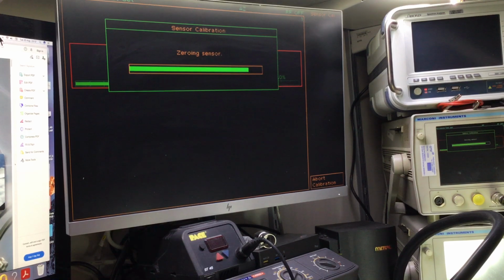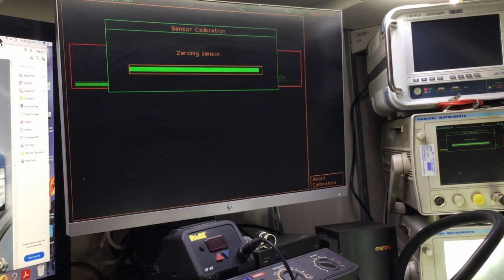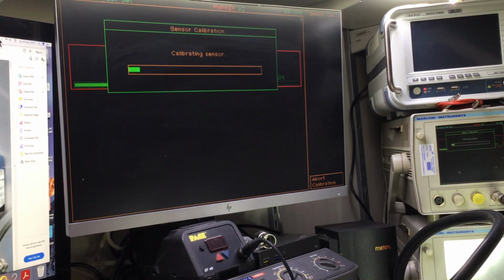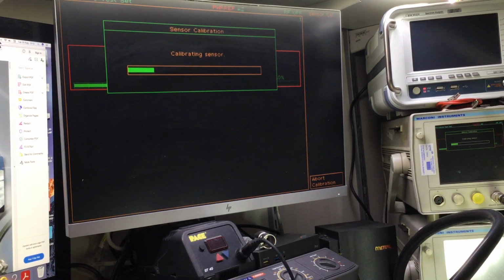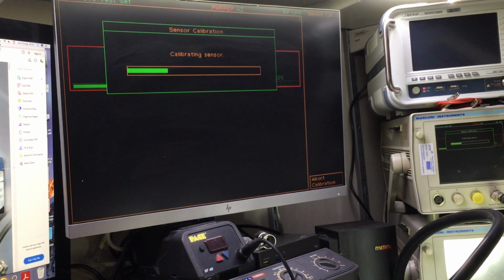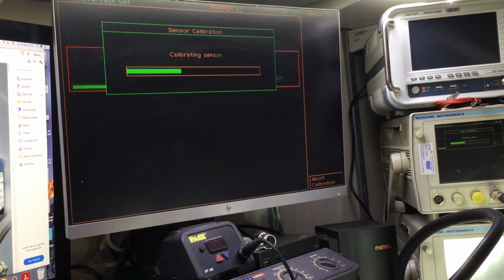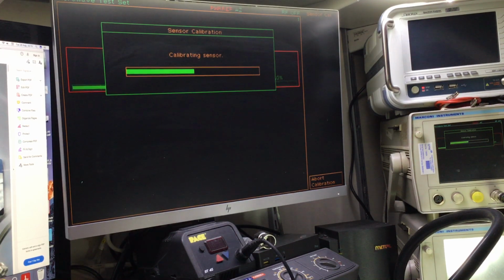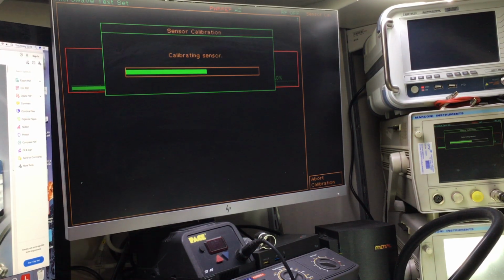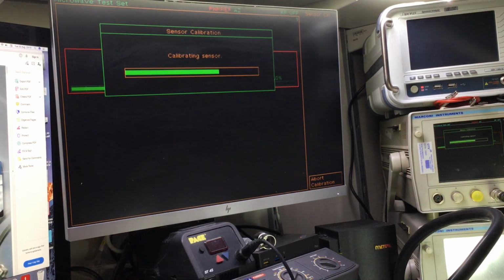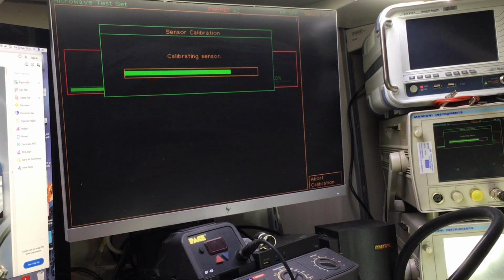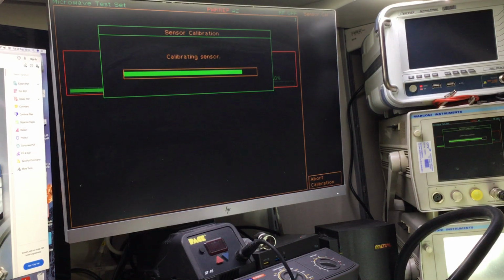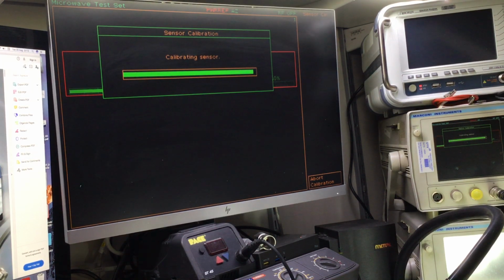So what I'm looking for essentially after this is the 0 dBm reference on the Marconi test set. It should read 0 dBm on this particular sensor. So I'll check that first, and then we'll move it over to the HP Agilent meter and test that, and then we can start testing the sensor.